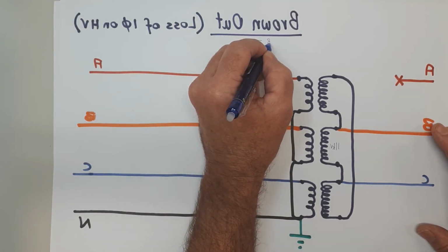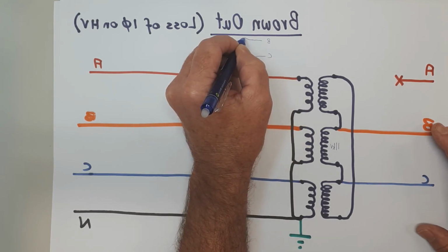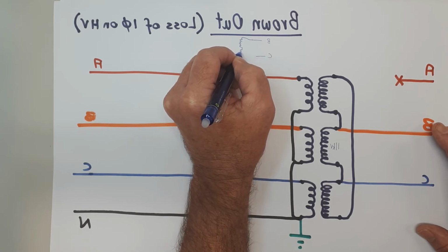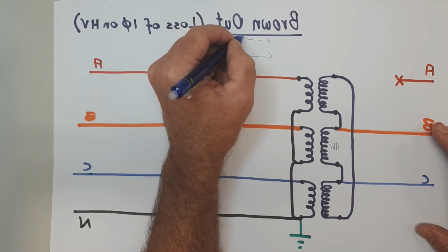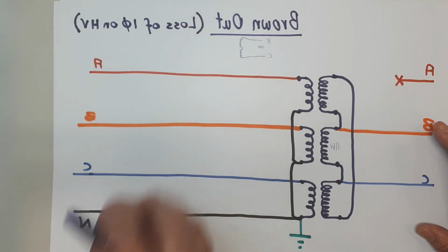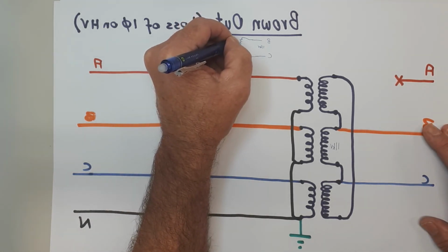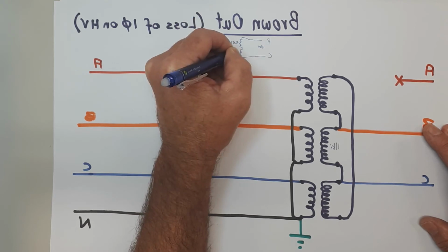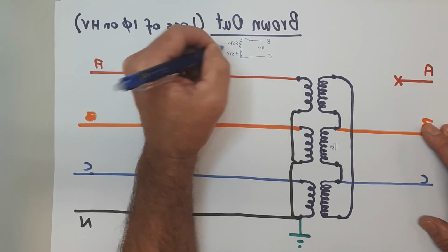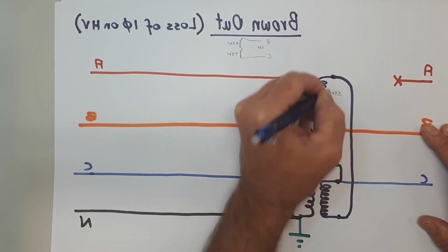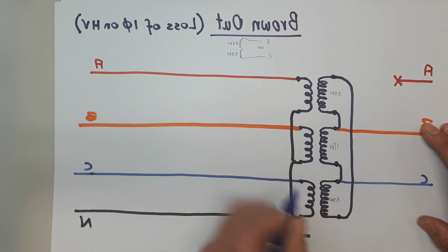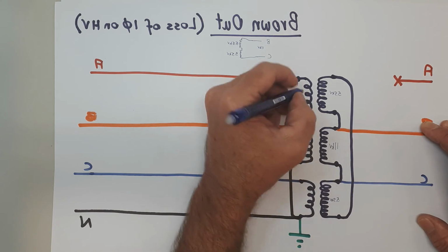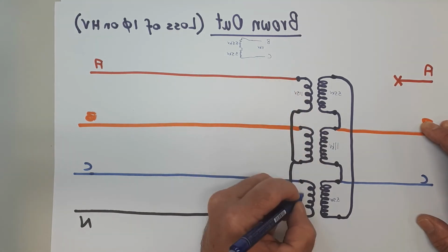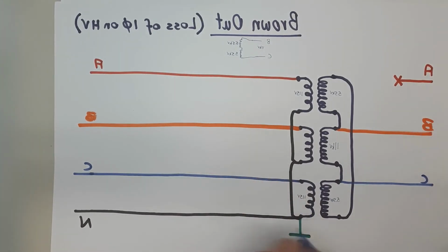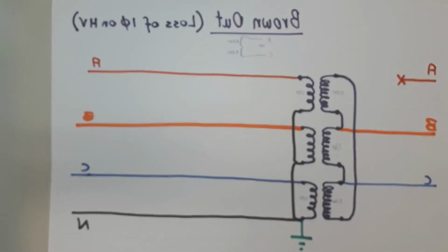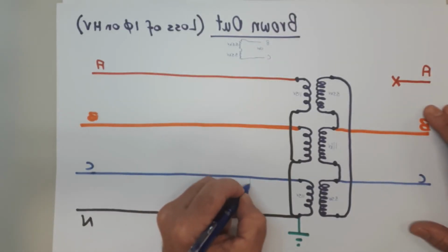There's B and there's C. It's like this. Winding, winding, and out. So they're sharing 11 kV. So that means they're going to split it, it's just a simple series circuit. They're going to split the voltage drop. So they're going to have about 5.5 kV on each of them. So that's what happens. All right, so now this winding's only being energized with half the voltage. So that goes down to 115 volts. And this one goes down to 115 volts. And so if your house is connected to C phase, you only get 115 volts.